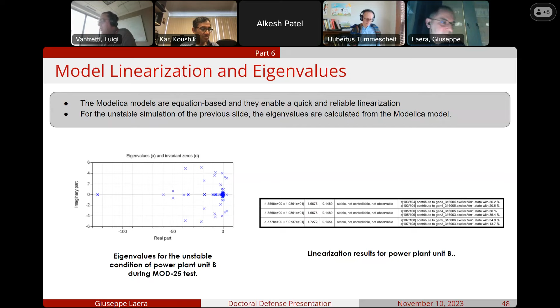And when the linearization is performed for the unstable loading case, the eigenvector analysis lists the existence of poorly damped oscillatory modes of approximately 1.7 Hertz, which are a result of the interaction between excitation systems from all 4 units present at the power plant where unit B belongs. So this interaction might be what is being observed in reality, since they have similar frequencies and they are also poorly damped.